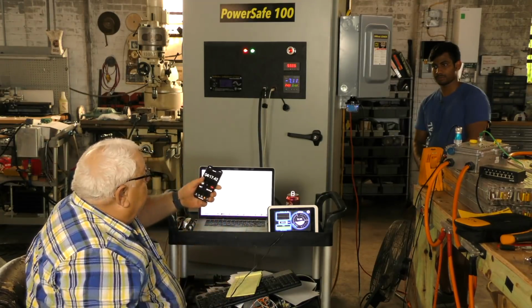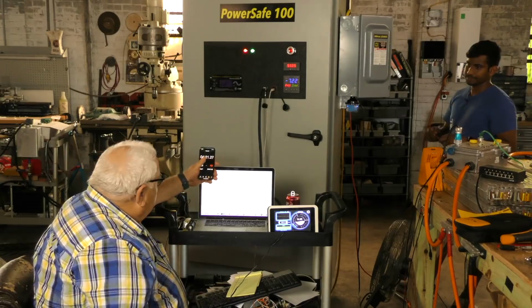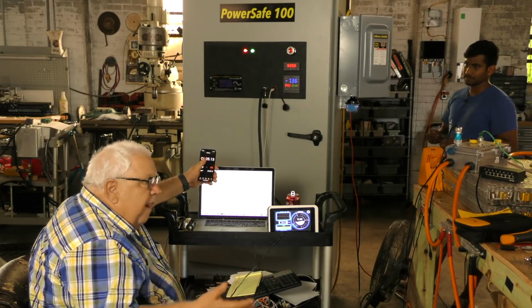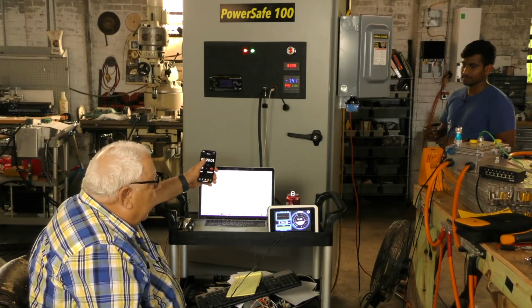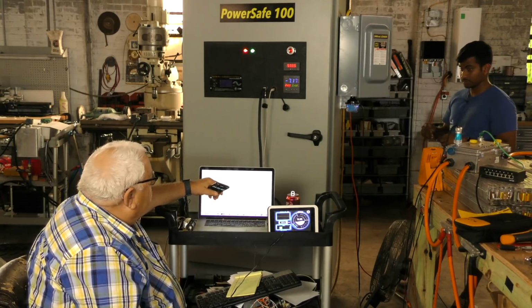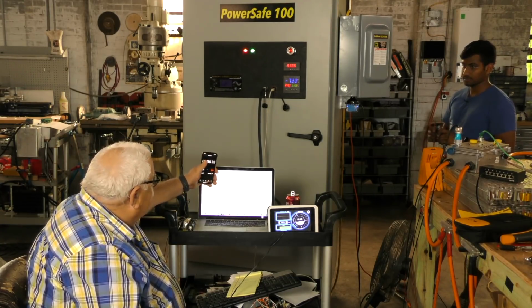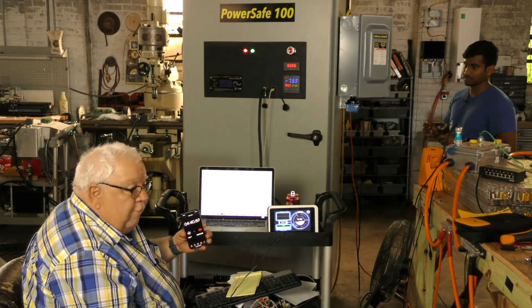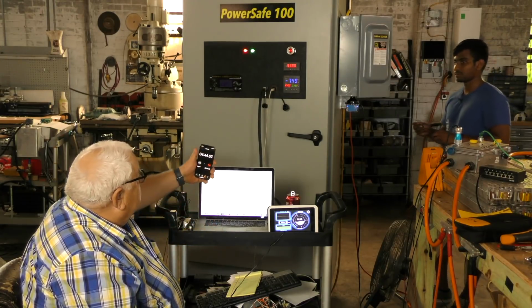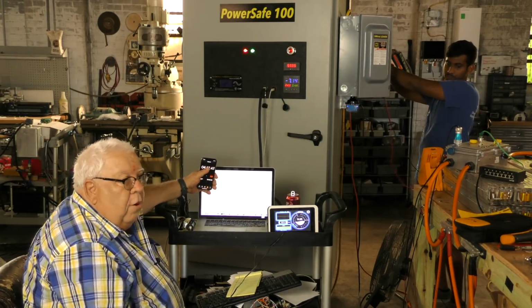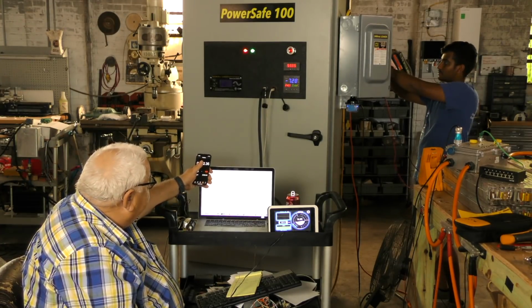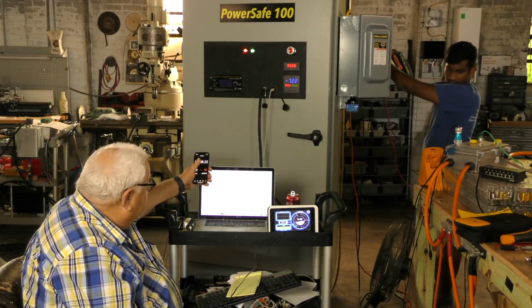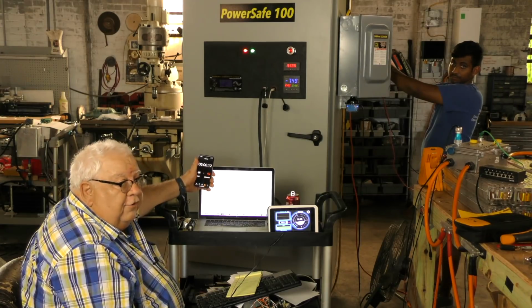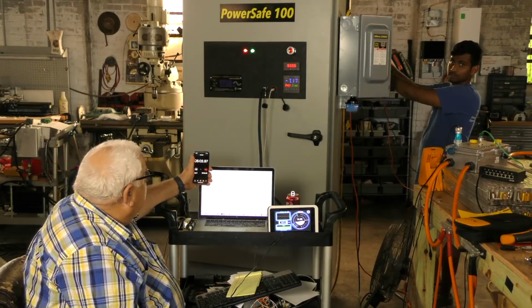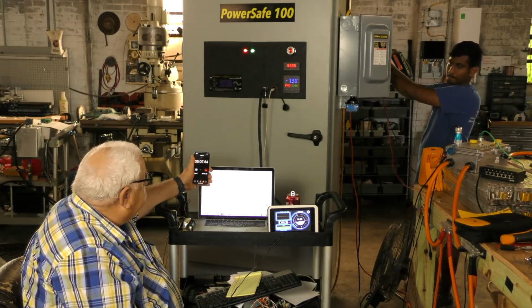Okay, we're at 4 minutes and 18 seconds. I'm still showing a discharge of 3.55 amps, right at 145 watts on our PowerSafe 100 inverter, and charge enable has been on for 4 minutes and 40 seconds. We're going to monitor that as we come up on 5 minutes. What we're looking for is a change from a very slight discharge of 145 watts to some form of charging. There's 5 minutes and no joy, we're still discharging. And there's 5:10, and it's not getting any better.